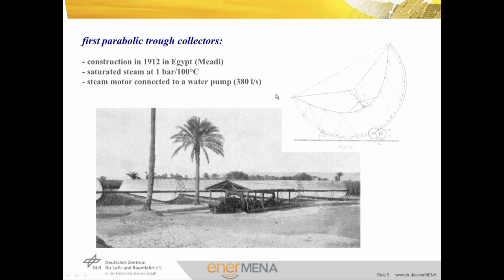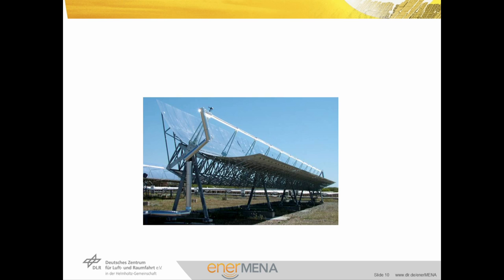Because the sun is moving during the day we need a special gear system in order to track the collector. 100 years ago the parabolic trough collectors were still simple because only 100 degrees and 1 bar were needed for operation. Today we would like to do electricity production with high efficiency and need about 100 bar and 500 degrees for operation, so we need a totally different collector — as you can see in this picture of a real modern parabolic trough collector.